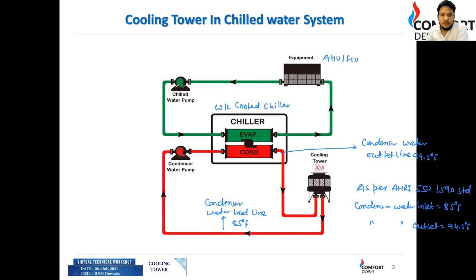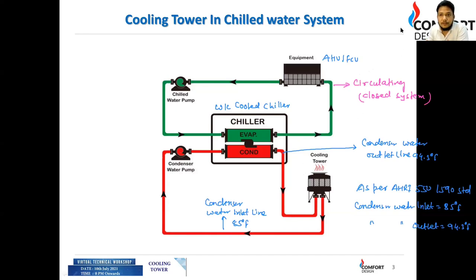Looking at this cycle, we find that the chilled water side is a closed system — water recirculates through that network. The condenser water side, where water comes in contact with the air in the cooling tower, is treated as an open system.